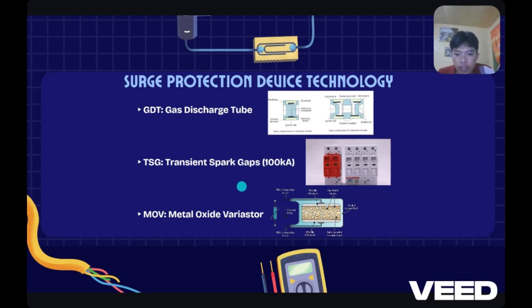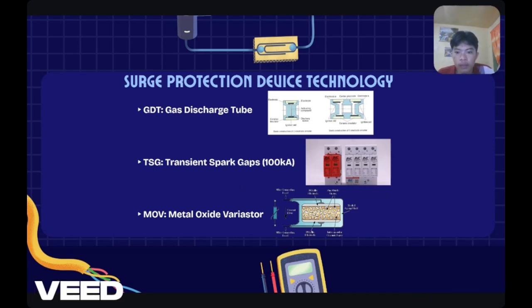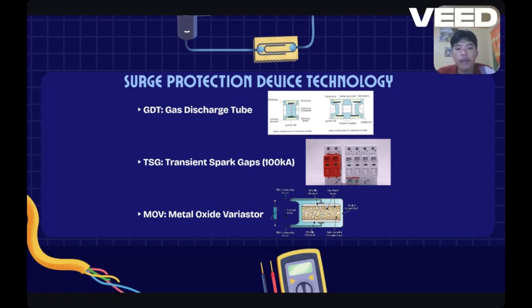Then transient spark gaps, up to 100 kiloamps, TSG. Transient spark gaps are devices typically used in residential or industrial electrical systems to protect equipment from voltage spikes and lightning strikes. Then metal oxide varistor or MOV. A varistor is a voltage dependent resistor that protects electronic circuits from high voltage spikes and surges. It acts like a safety valve for electricity.